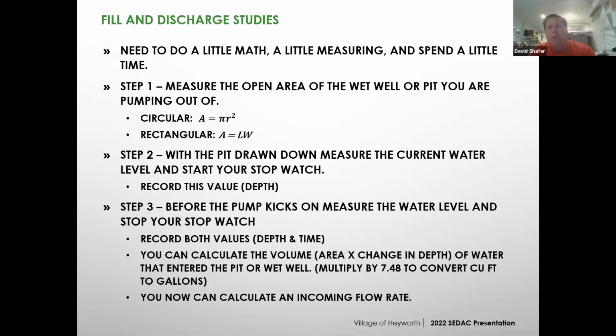For a fill and discharge or fill and draw study, it's a little bit of math, a little bit of measuring, and spending some quality time at your lift station of choice. First, you need the open area of the wet well or pit you're pumping out of. If it's a circular wet well, it's pi times the radius squared—so measure your diameter, cut it in half, and square it.